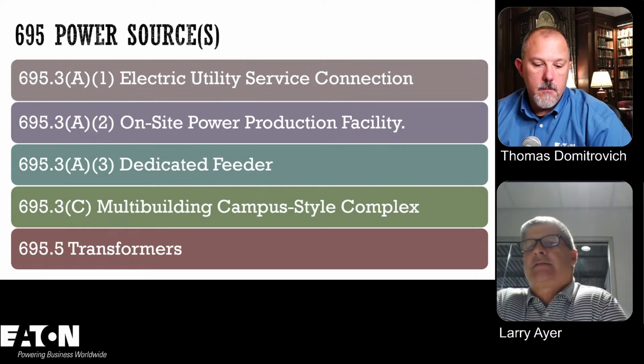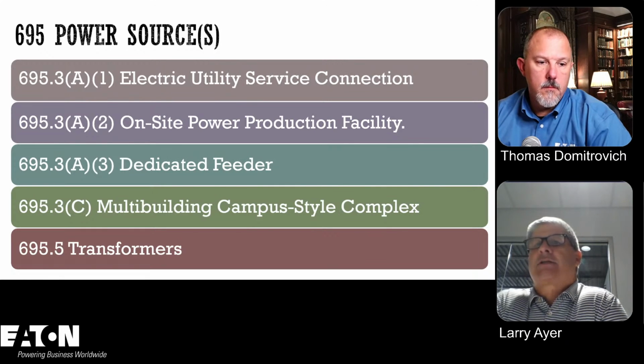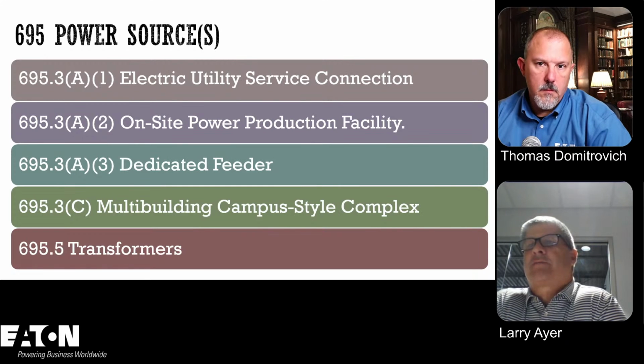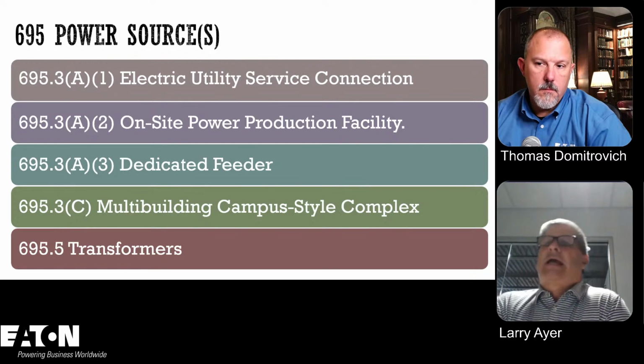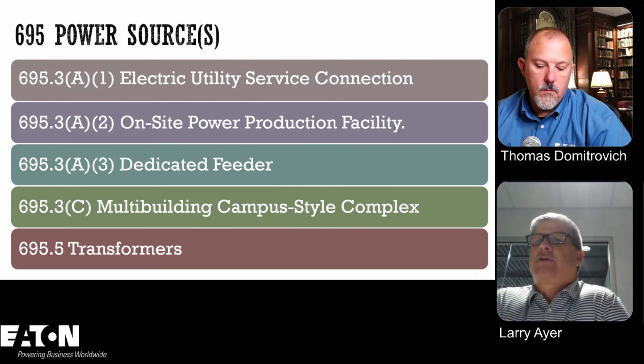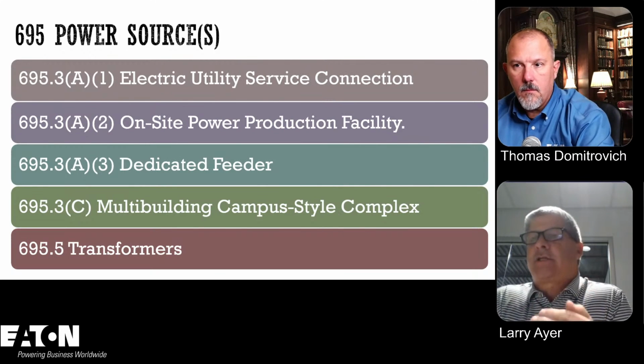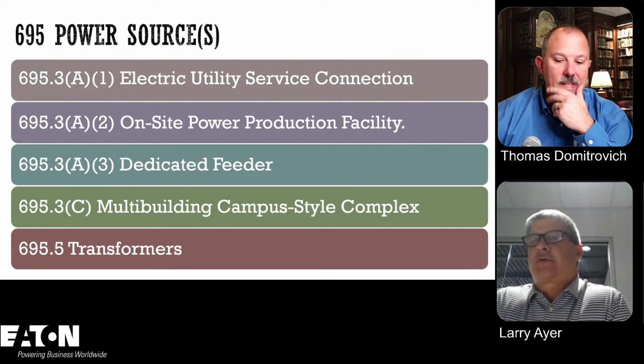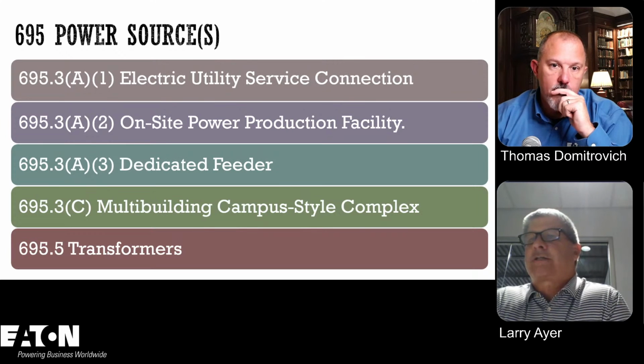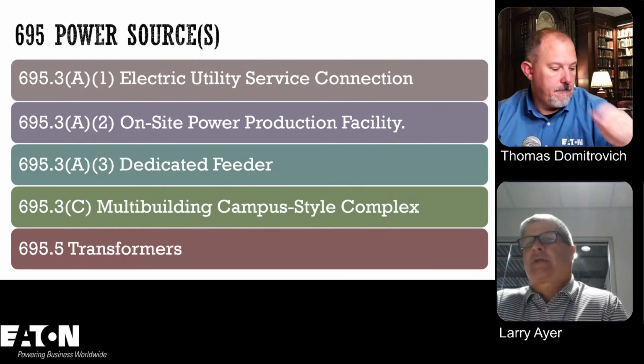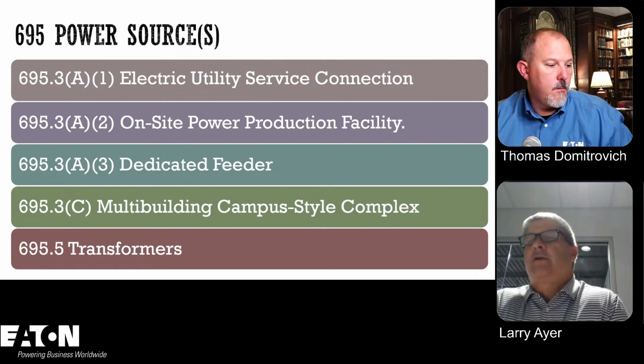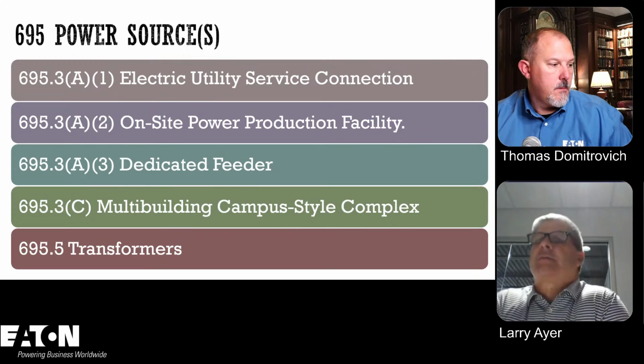So in these situations, and I think it's mentioned in NFPA 20, if you have a feeder that has more than 1 disconnect, you can step that down, but then you're going to need an alternate source of power because you have more than 1 disconnect. I know some AHJs are sticklers for this. I've seen people say you have to take a 13.2 feed to a 13.2 to 480 step down transformer with no overcurrent protection, and then hit your fire pump. Other people said, well, I'll let you do that if you put in an alternate source of power. So I've seen a couple of different arguments.